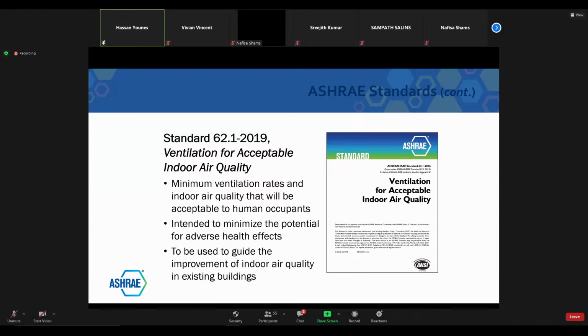Another thing that we look at in standard 62.1 is the exhaust requirements. So it will tell you for a toilet what would be the amount of exhaust needed. Also, it looks at air classification. So an office building would be class 1, whereas let's say a toilet will be class 2. The higher the class, the more concentration of pollutants there is, and you cannot mix between classes. If you mix, let's say, class 1 and class 2, automatically that whole air stream becomes class 2. So a lot of information on indoor air quality.